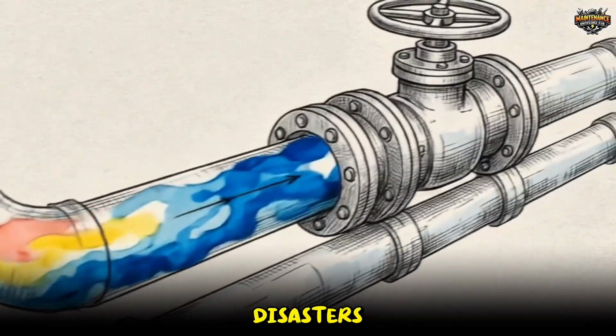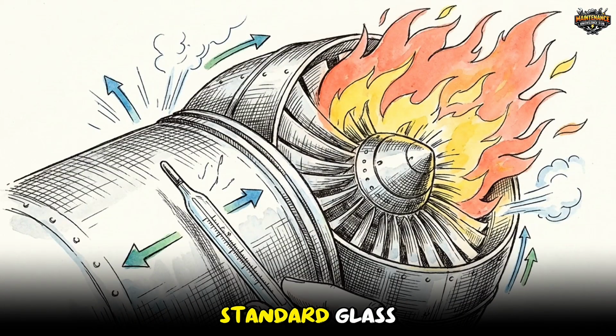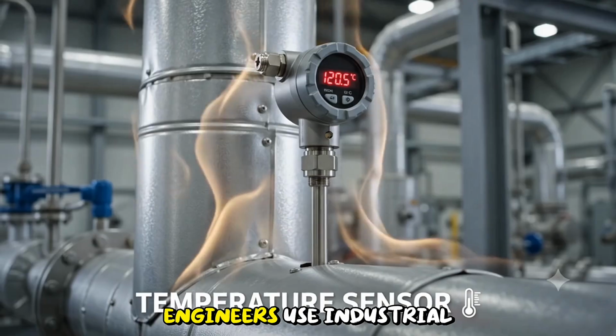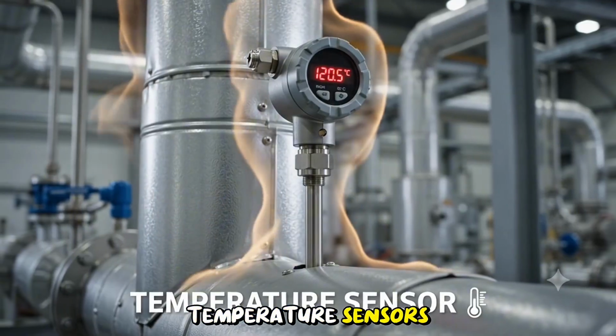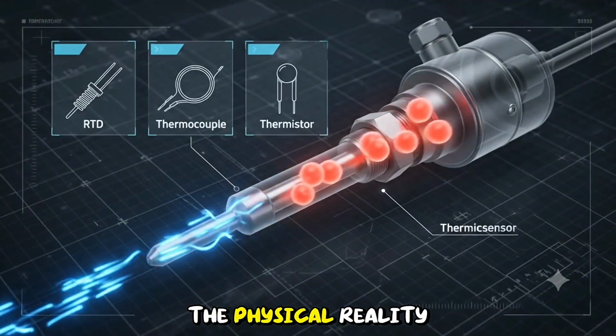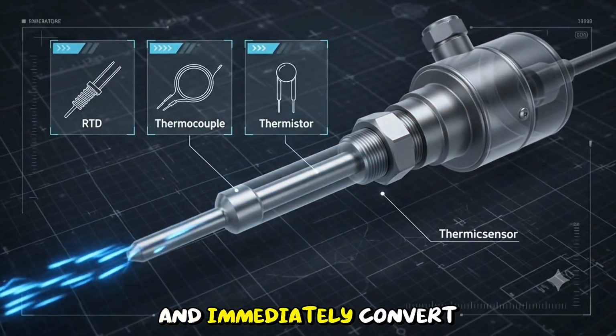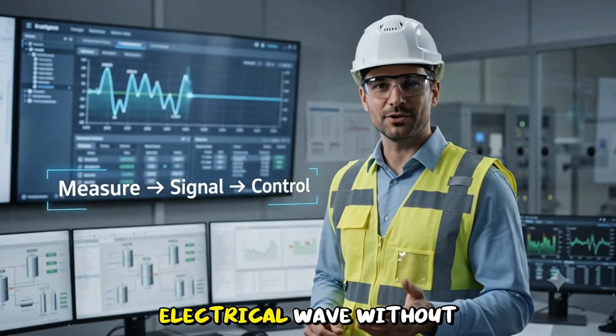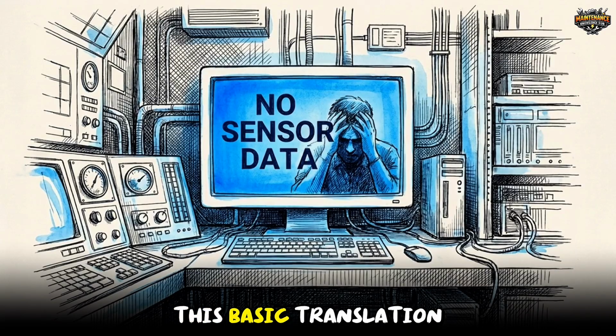physical disasters. You obviously can't just stick a standard glass mercury thermometer into a 1,000-degree gas turbine and expect a reading. Instead, engineers use industrial temperature sensors. These devices detect the physical reality of the heat and immediately convert it into a pulsing electrical wave. Without this basic translation from physical heat to digital data, the modern computers controlling these facilities would be completely blind.